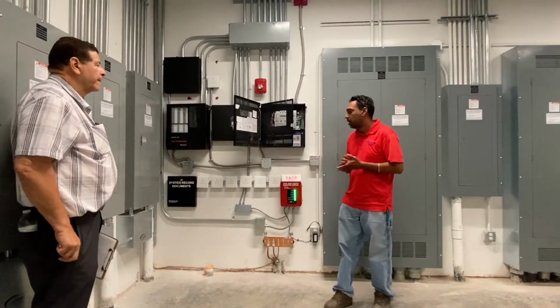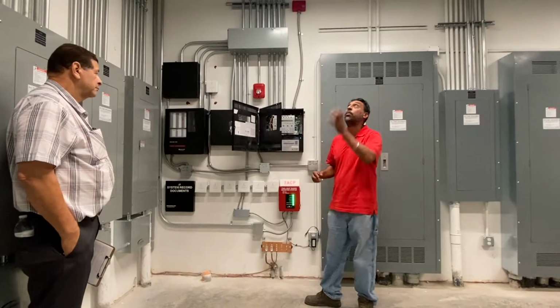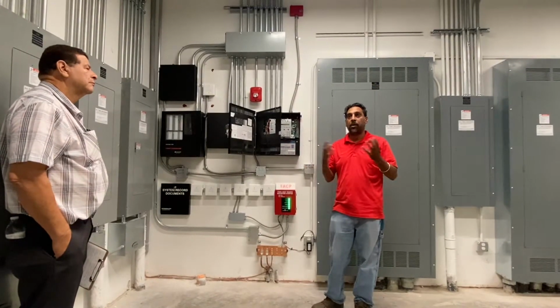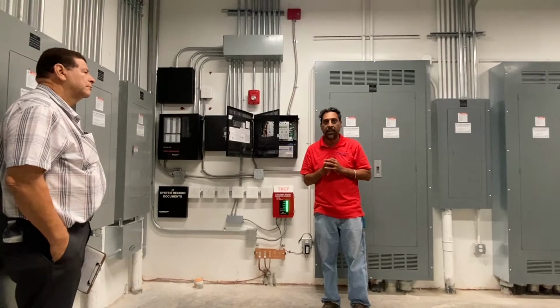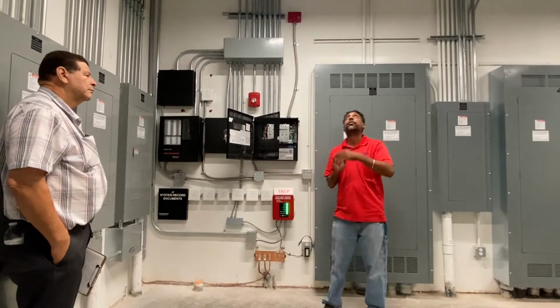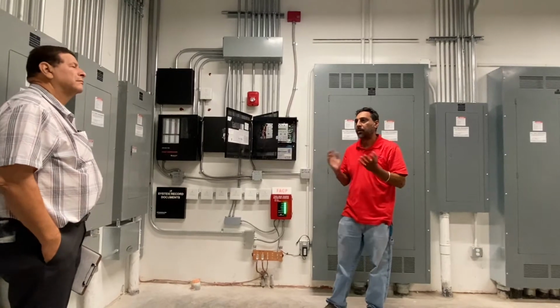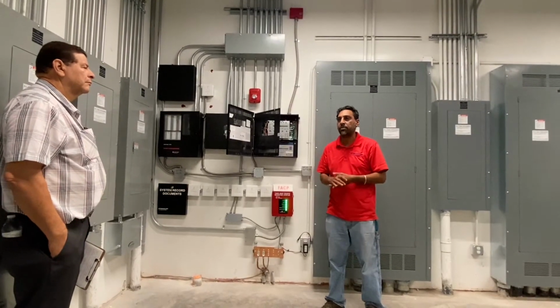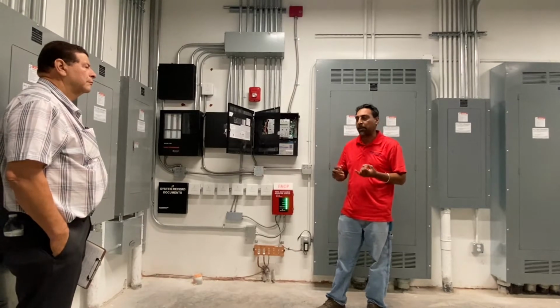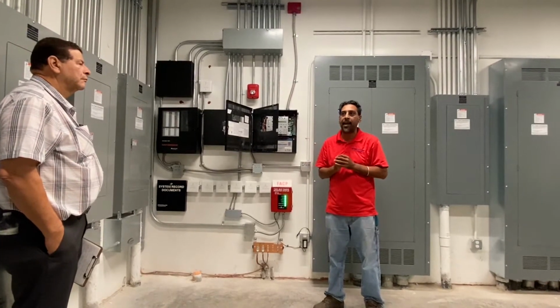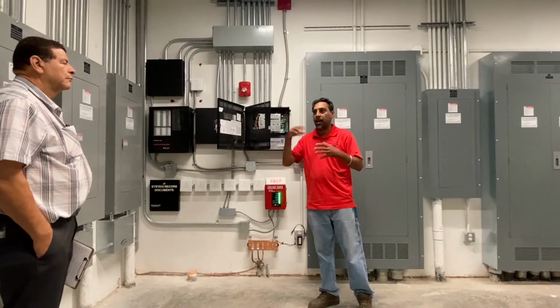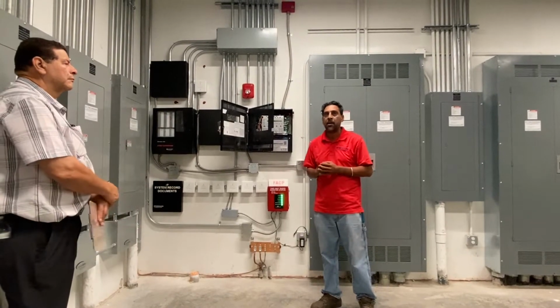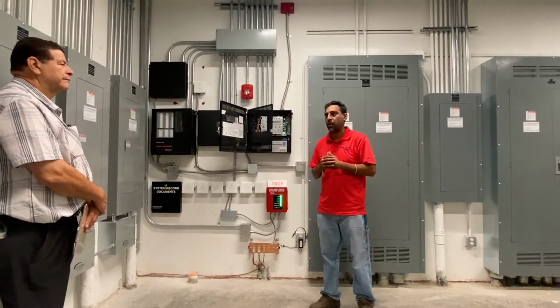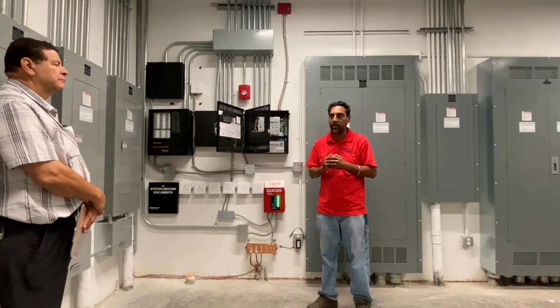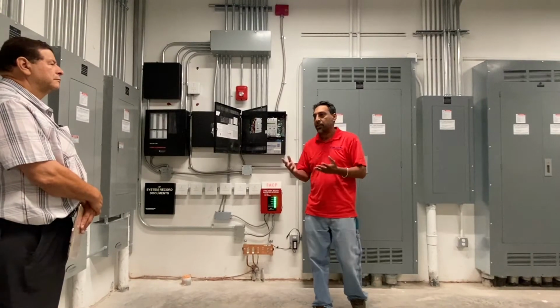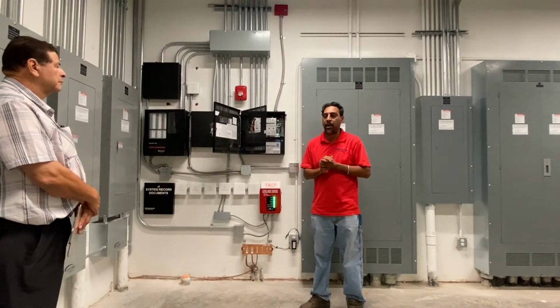On your troubles, a couple of the troubles that you have is if someone pops a device off, or if we have a smoke head going dirty, or it's out of calibration. For instance, this one will say smoke detector, first floor electrical room, and the electrical room number. If you get an invalid reply, that means the addressable system, which is always polling and looking out for the devices constantly at light speed, doesn't see that device. So it'll give you a trouble saying invalid reply, it's not talking back to me. One thing about your troubles, you can sit here and hit reset all day, it will not clear.